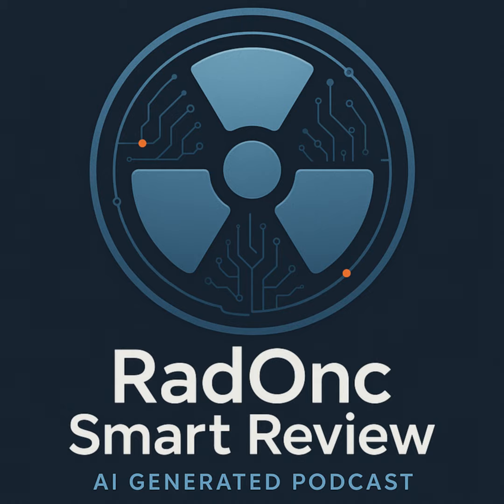See? You need significantly more MU when the wedge is in. You're essentially running the machine longer to push enough radiation through that attenuating wedge. That's why the WF is always in the denominator. Dividing by a number less than 1 makes the result bigger. That makes perfect intuitive sense. Direct compensation.